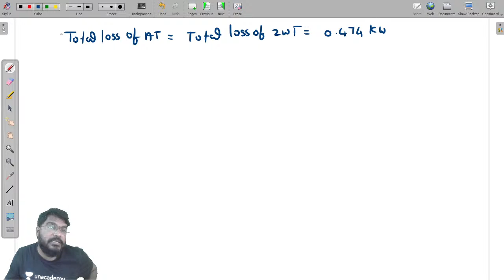Okay, 12 divided by 0.962 is equal to 12.47 minus 12, which is equal to 0.474 kilowatts. So these are the losses of the two winding transformer. But what about the total loss of the auto transformer? Total loss of auto transformer is equal to the total losses of the two winding transformer, so that is equal to 0.474 kilowatts. But percentage losses are different, but we don't want to find percentage losses. So very important this one.